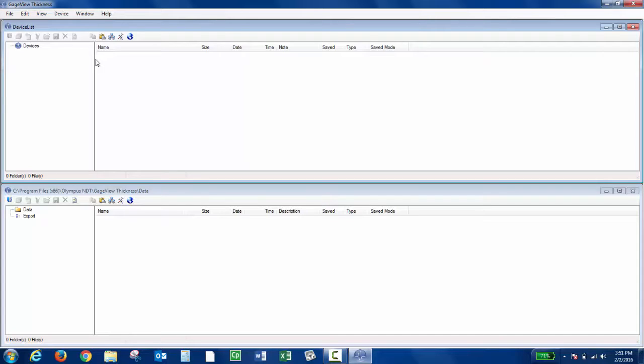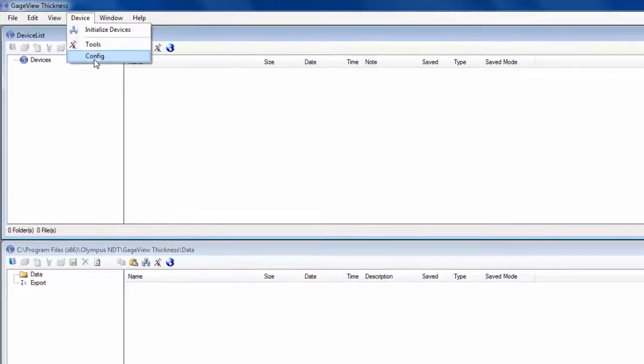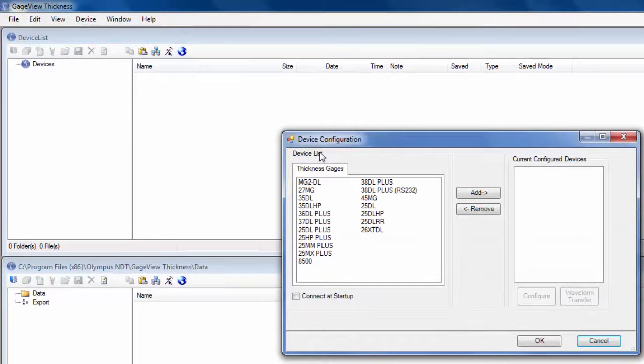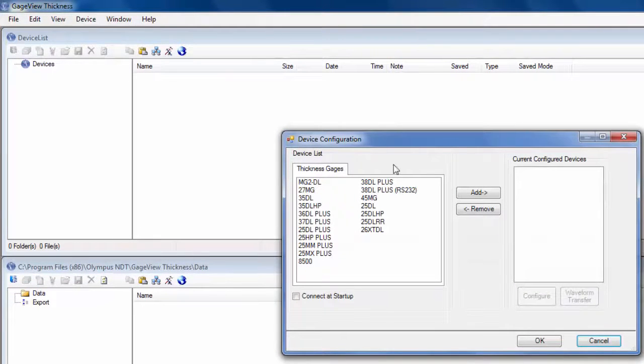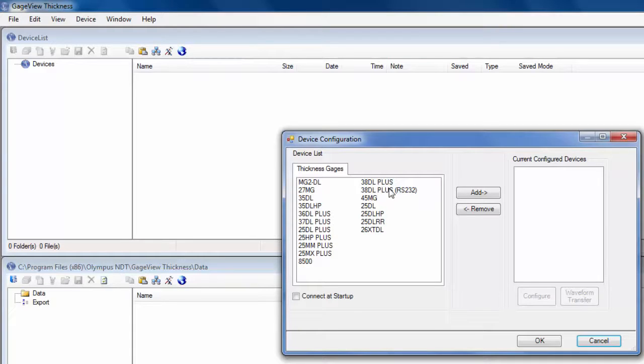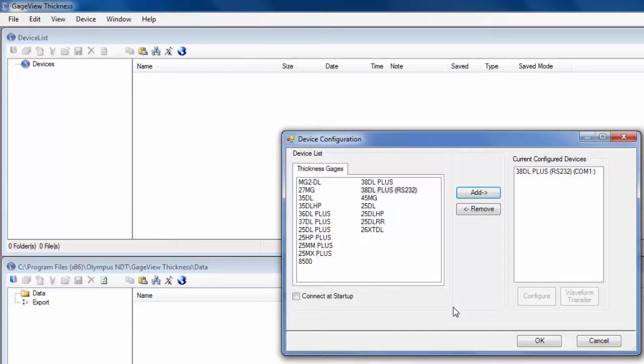The next thing you'll want to do is initialize the instrument. Click Device and then Config. You have your device list with all the instruments, and then you also have your current configured devices. The 38DL Plus has two options. Since we're connecting through RS-232, we're going to choose that one and then click Add. If you want GageView Thickness to automatically initialize the instrument when you open the program, you can check off Connect at Startup.